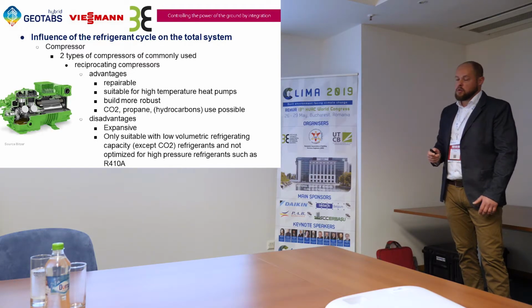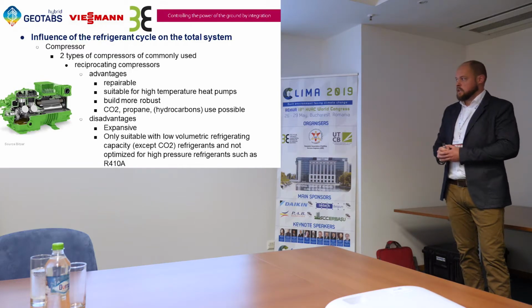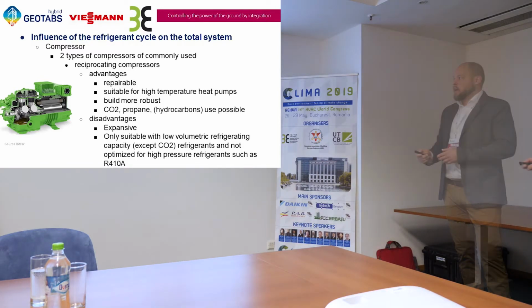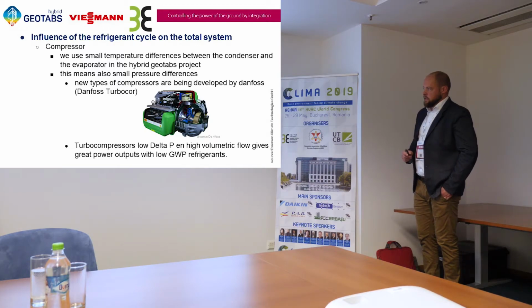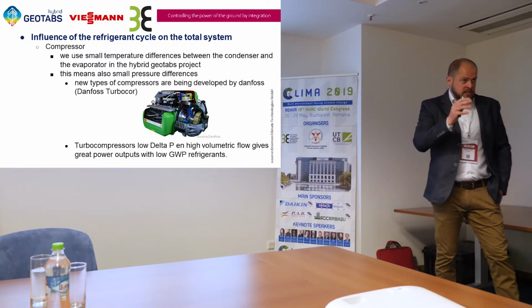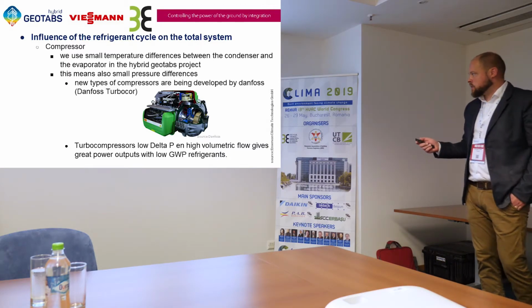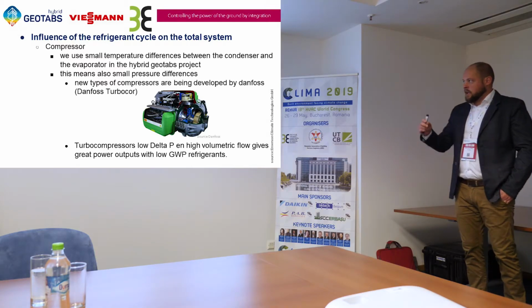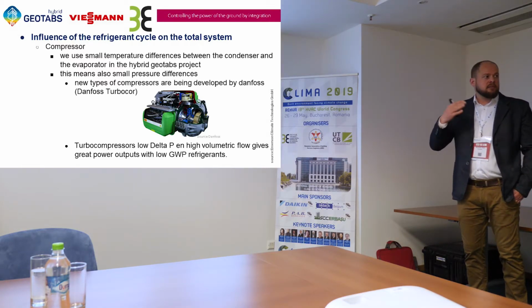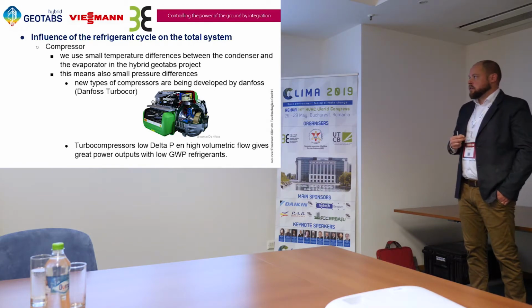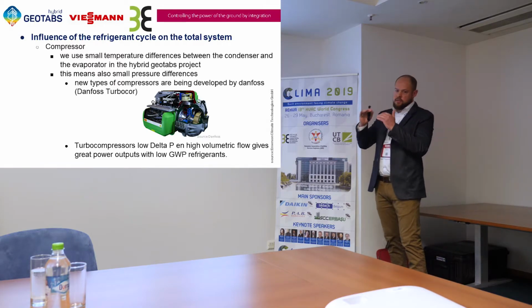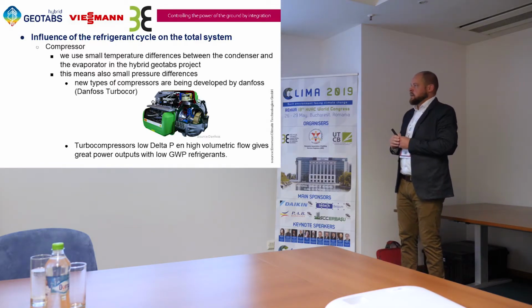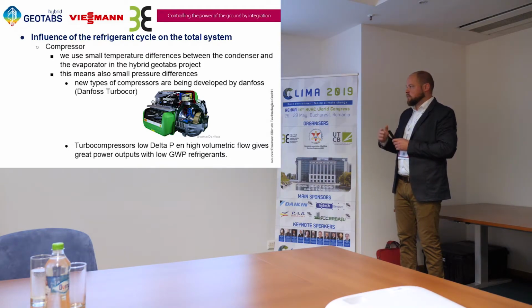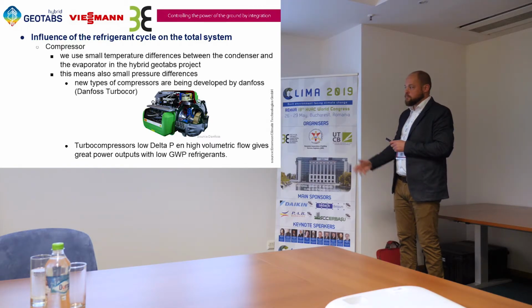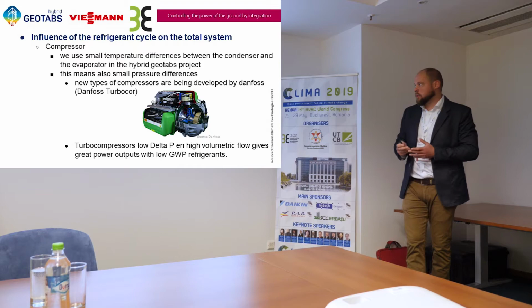That's the reason why in the standard Viessmann heat pumps today, we mostly use scroll compressors. Another development that I saw at Danfoss is a new type of turbo compressor. The principle of it is like a hydraulic pump. We suck the refrigerant into the compressor, and it works with a lower delta P but a high volume flow. So it's typically for the hybridGEOTABS project, where we work with low temperature differences between the source and the condensing side. This can be a very interesting type of compressor, also for the newer refrigerants. So that's something we will look at in the future.